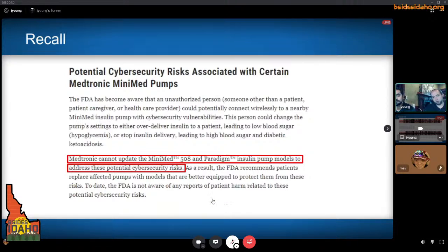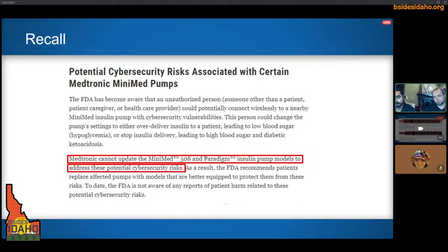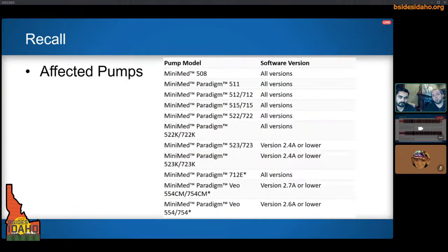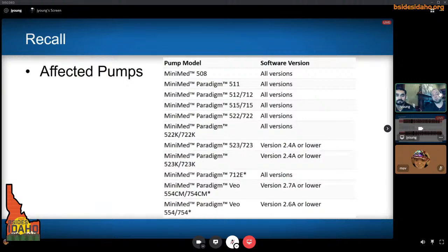So the primary reason for the recall, beyond the obvious patient safety risks, is that that pump is not programmable or updatable. There's no mechanism to update the firmware. The device is locked as manufactured. And additionally, the recall affected multiple versions because in addition to the 508 pump that we were experimenting with, that transmitter receiver pair or circuitry was used across a number of models. You can see here the 508 in addition to a number of MiniMed Paradigm models as well.